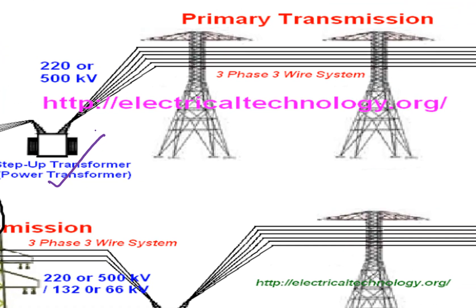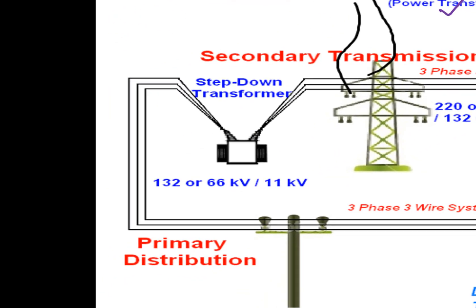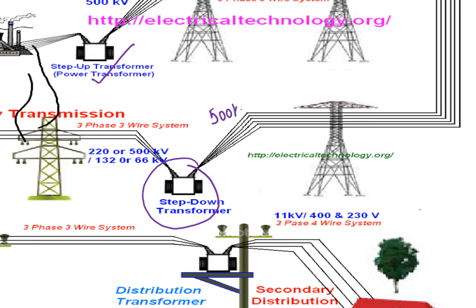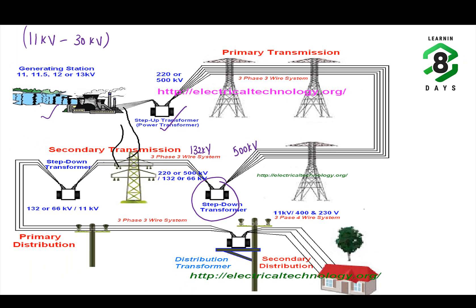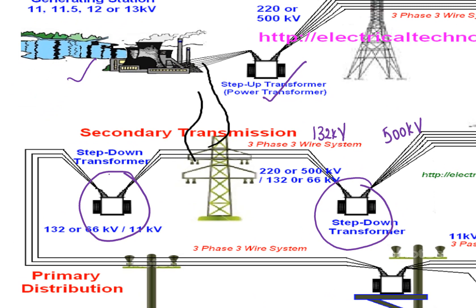This is the primary transmission. Then there is a step-down transformer at a substation where the voltage is stepped down from that high voltage to a medium voltage — for example, from 500 kV down to 132 kV. Secondary transmission then occurs at 132 kV. In the vicinity of any town or city, there would be another step-down transformer in a substation, stepping the voltage down from 132 kV to 33 kV or 11 kV.